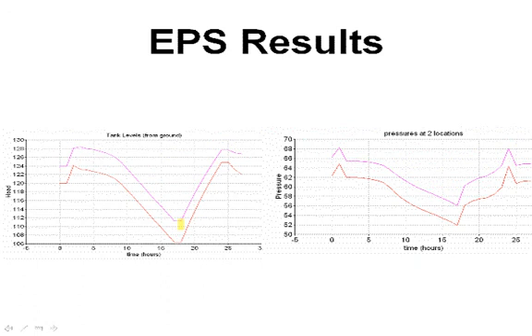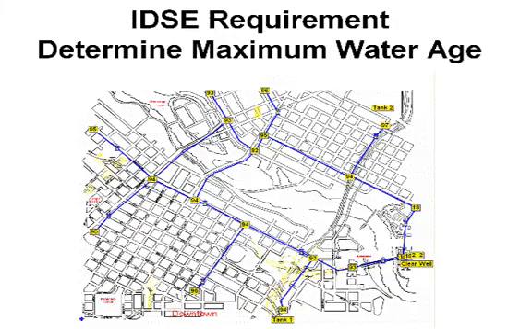When you run this, you'll see, for example, the tanks going up and down. As the tank goes down, the pumps kick on, and the tanks go back up again. Pressure variations range from a high of 68 down to a low of around 56, quickly showing you the variations in your system over a typical day.